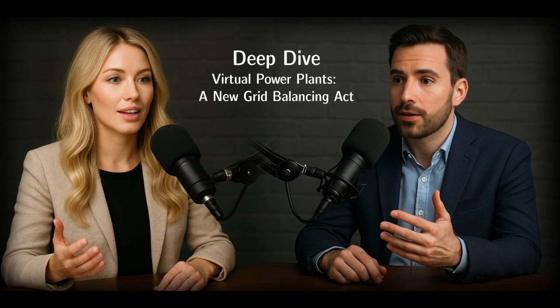Beyond just managing demand levels, the more sophisticated VPPs can provide critical ancillary services. These maintain overall grid stability, kind of like the grid's shock absorbers. This includes frequency regulation, where the VPP makes rapid, small adjustments to power injection or withdrawal, maybe within milliseconds, to keep the grid's frequency stable right around 60 hertz. Keeping everything in balance.